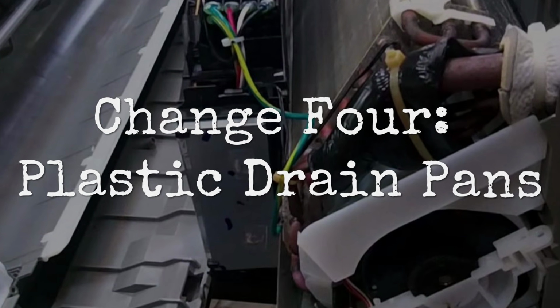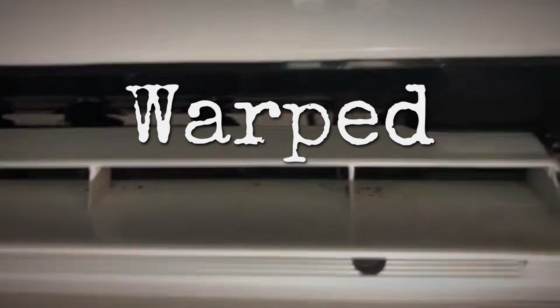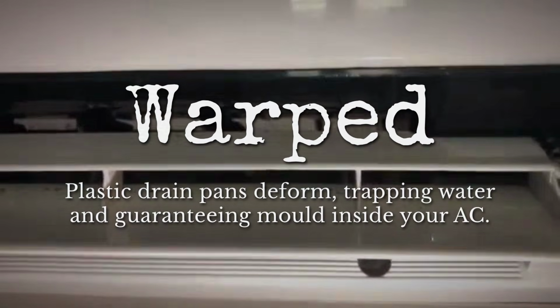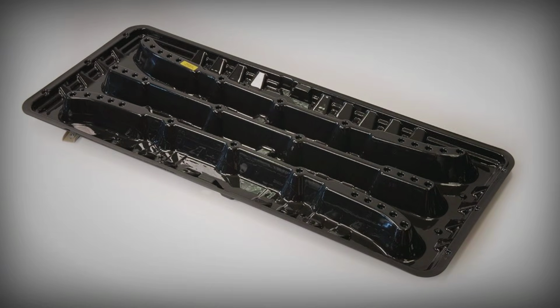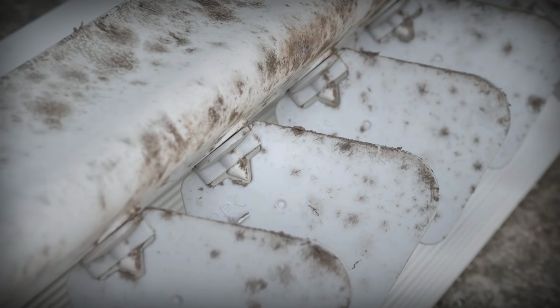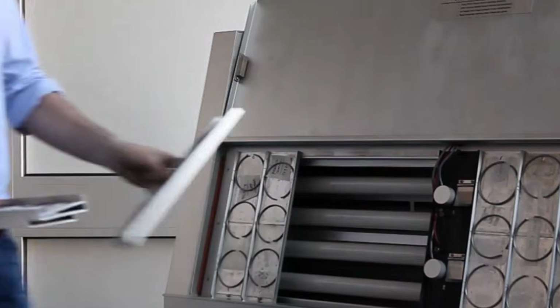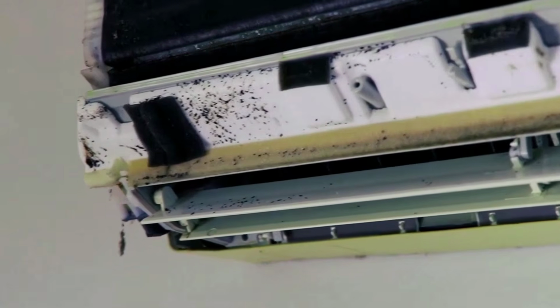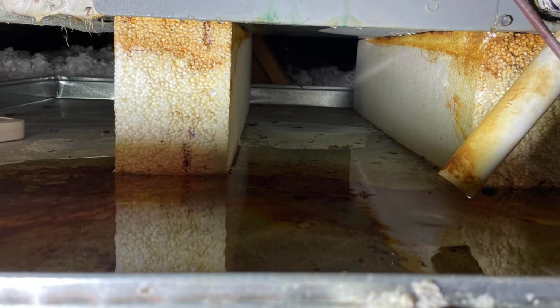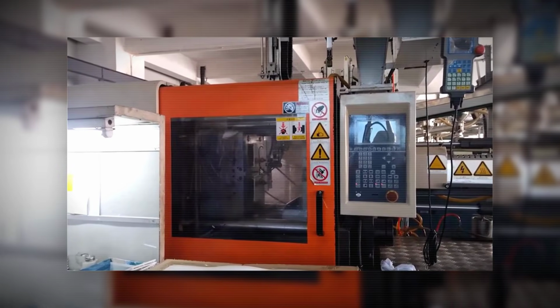Change 4. The drain pan and housing materials. Every internal housing component on a modern residential split system is injection molded plastic. The drain pan, the fan barrel, the louver arms, the bracket clips. All of it warps under heat cycles, degrades under ultraviolet, and produces the mold problems every Australian eventually discovers when they pull the cover off after a long summer. A warped drain pan does not drain. Water that does not drain sits, and mold that sits grows. That is not a cleaning problem. It is an engineering decision made in a factory in Guangdong that you paid for with your credit card.